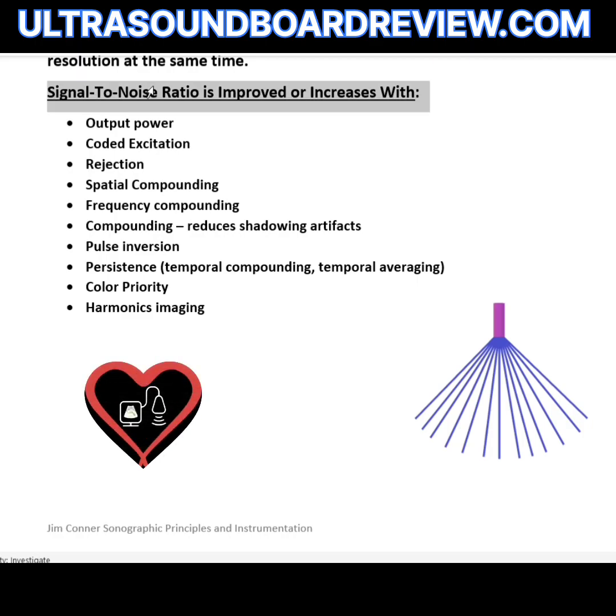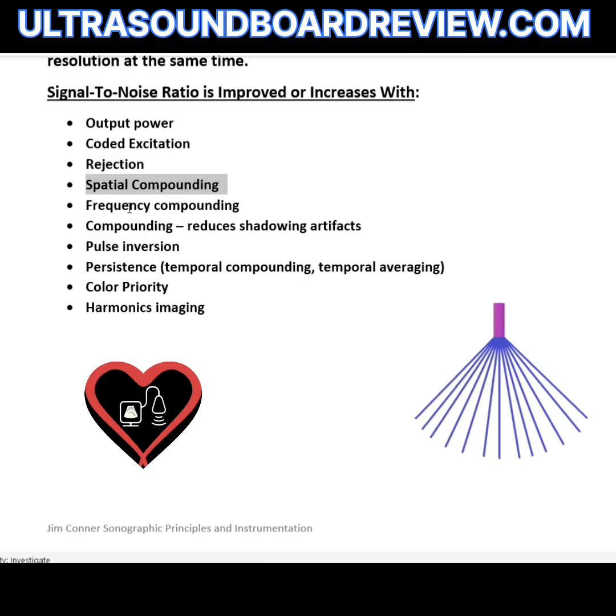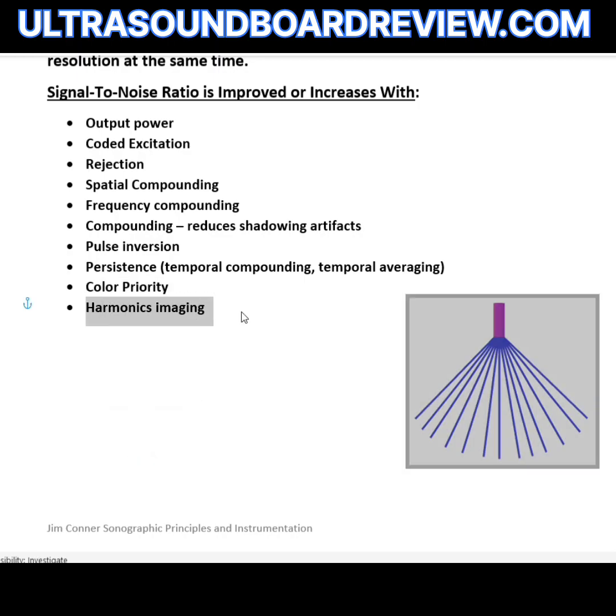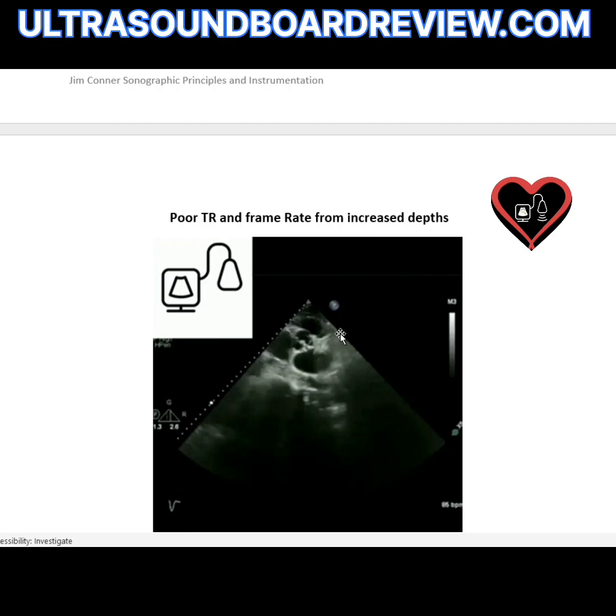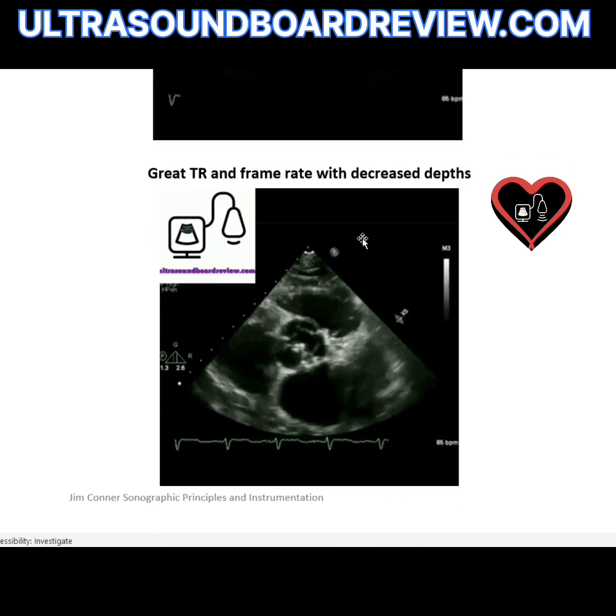Things that improve signal-to-noise ratio include: output power, coded excitation, rejection, spatial compounding or frequency compounding (any type of compounding), pulse inversion, persistence (also called temporal compounding and temporal averaging), color priority, and harmonic imaging. As shown in these images, increasing depth degrades temporal resolution and frame rate, while decreasing depth results in much better frame rate and temporal resolution.